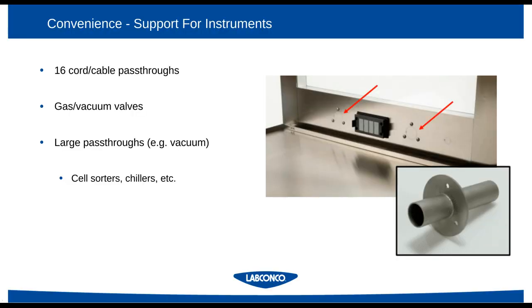And lastly, some instruments require quite unique pass-throughs. So if you are working with something that requires a vacuum line, or especially if you're working with a cell sorter that has a requirement for an airflow management system, those systems can be easily passed through with specialty flanges on our enclosures to allow for compatibility with all types of instruments.